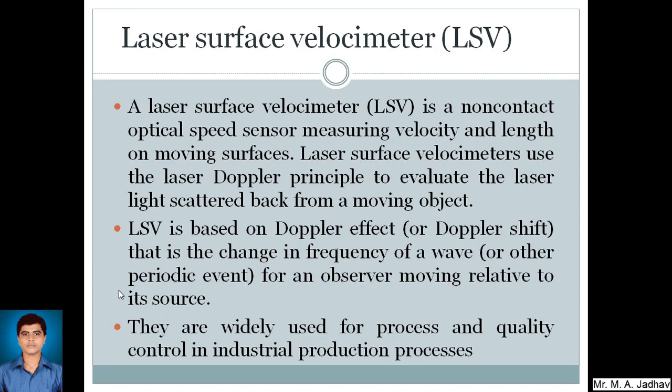The next is laser surface velocimeter, that is LSV. A laser surface velocimeter is a non-contact optical speed sensor measuring velocity and length on moving surfaces. Laser surface velocimeters use the laser Doppler principle to evaluate the laser light scattered back from a moving object. LSV is based on the Doppler effect or Doppler shift, that is the change in frequency of a wave or other periodic event for an observer moving relative to its source. They are widely used in processes and quality control in industrial production processes.